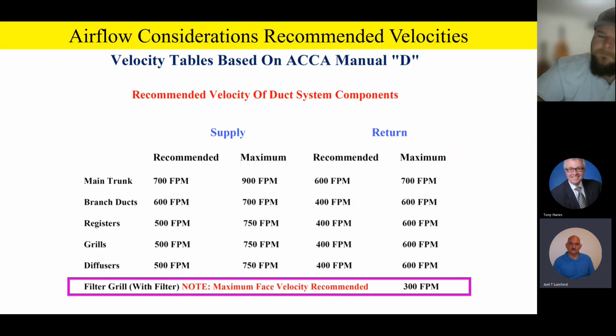So this becomes really important, especially if you've got applications where maybe you've got a home, maybe it's a 3-ton unit in this home that's got just one large return in the hallway or something like that. And the homeowner maybe wants to put in one of those pleated filters that you buy from a hardware store or big box store, that are very, very restrictive. So we want to make sure that we do not exceed 300 feet a minute velocity across our filter grills if we have a return grill with a filter in.